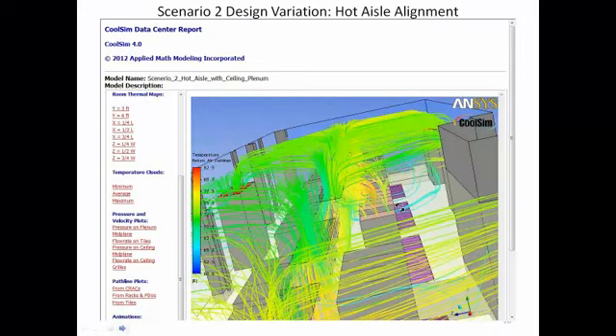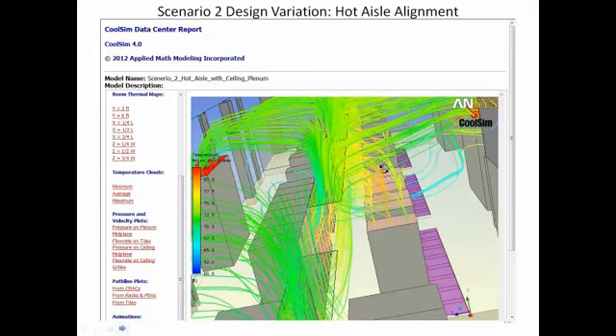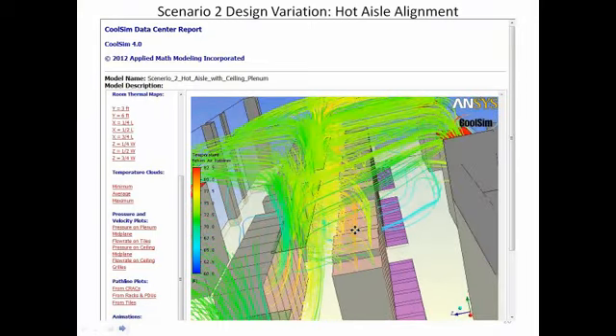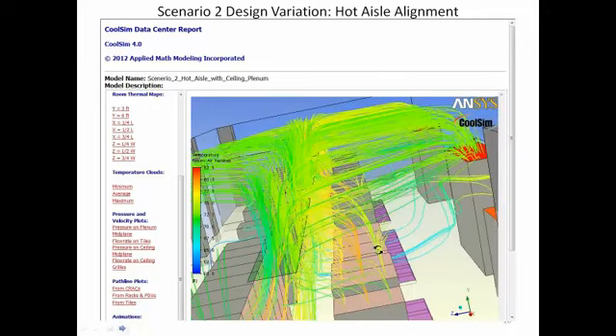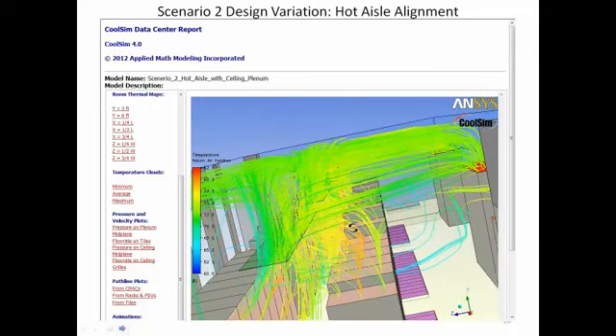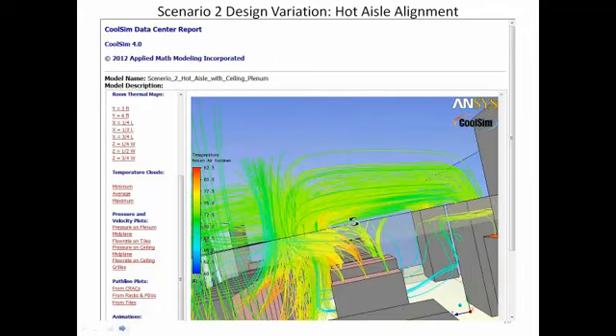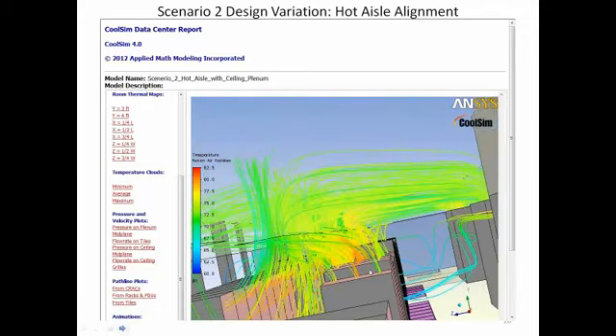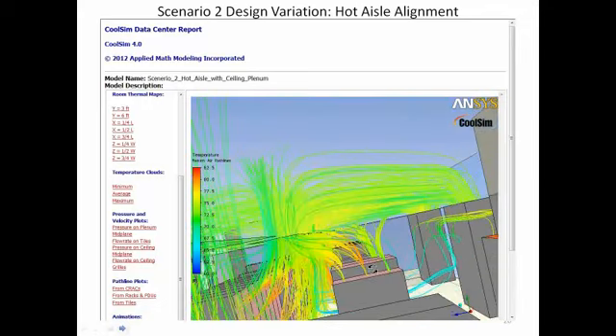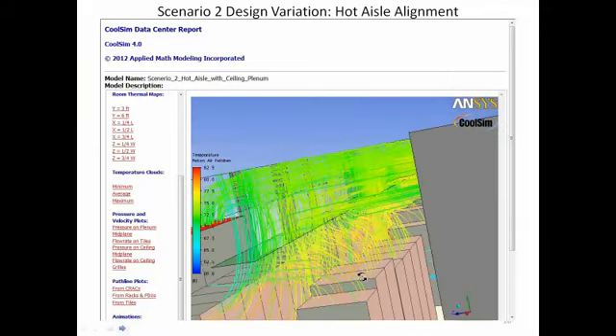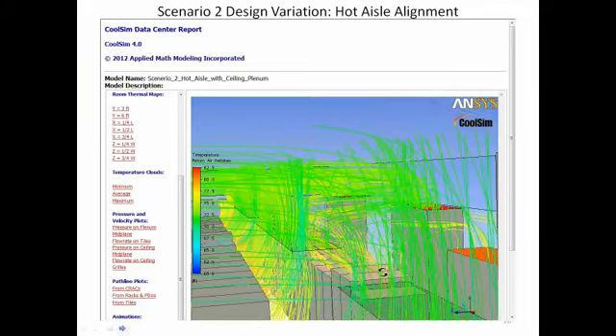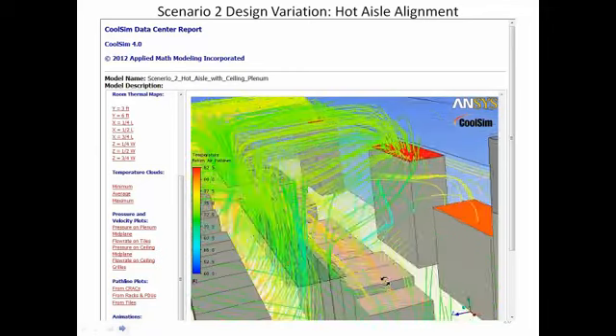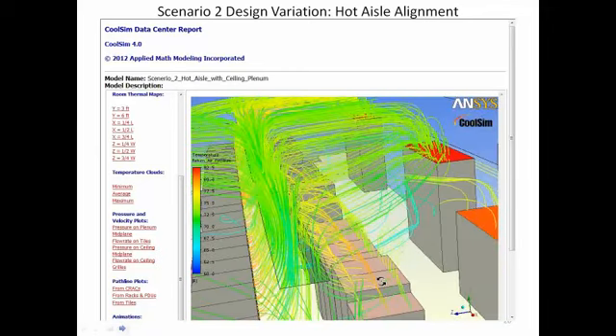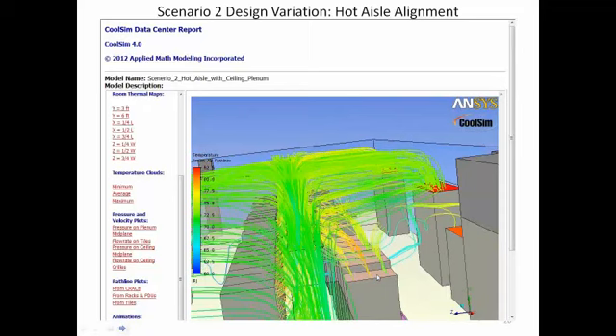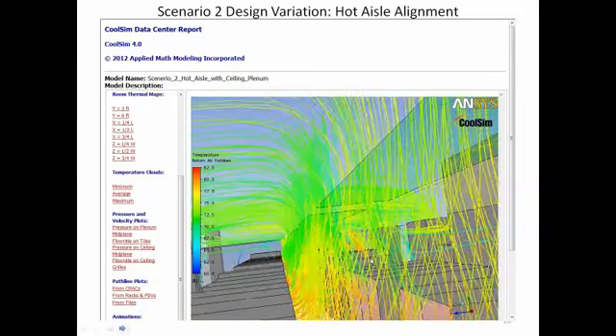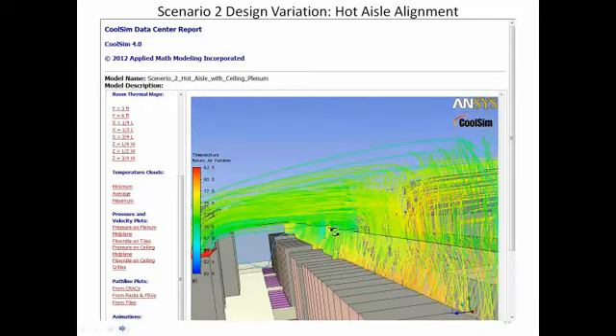Now, I think the plan you were saying was eventually for them to swap these out. So yes, there's two things they could do here. One is put more ceiling grills in. It doesn't really hurt to have too many unless they get too close to these front ones. But the other thing you could do is try putting some curtains in place on those, either one. We're not containing here. You haven't contained anything. All you've done is really just line it up and use that return plenum. Correct. Just trying to do it for better airflow management.